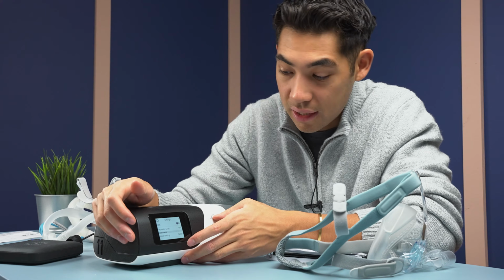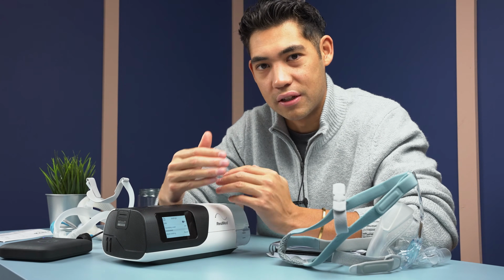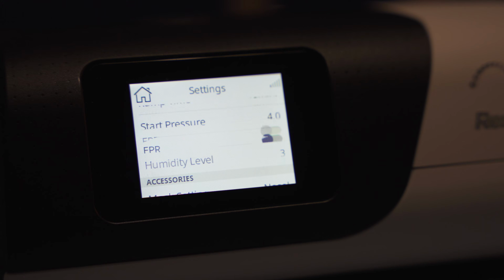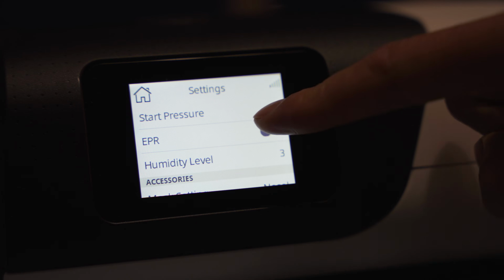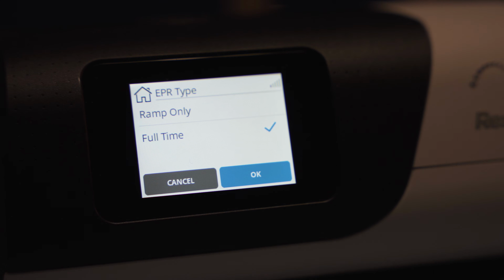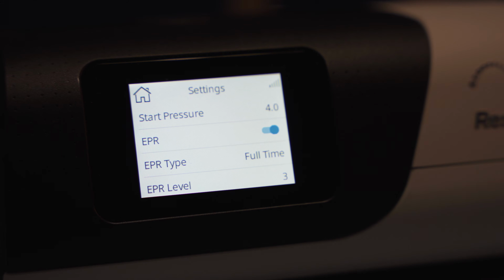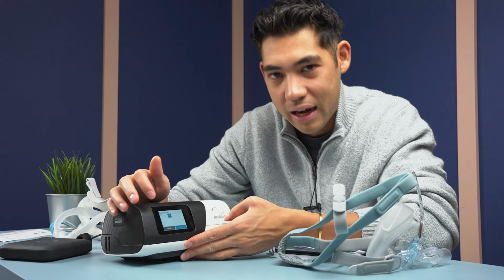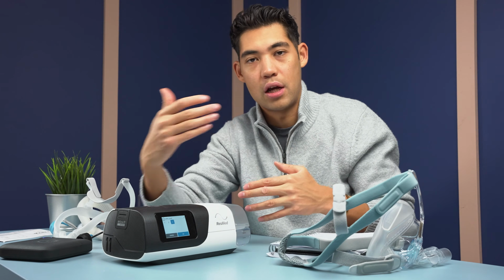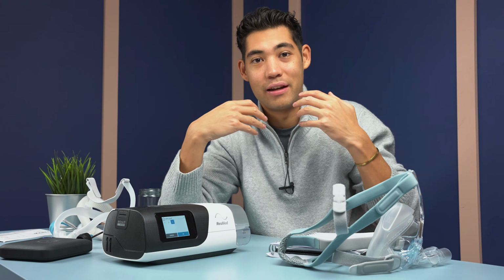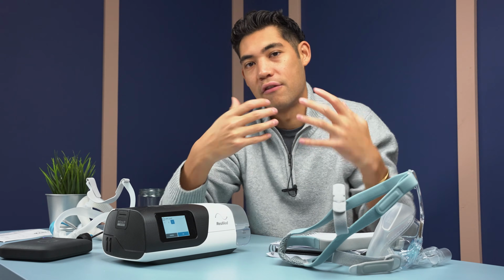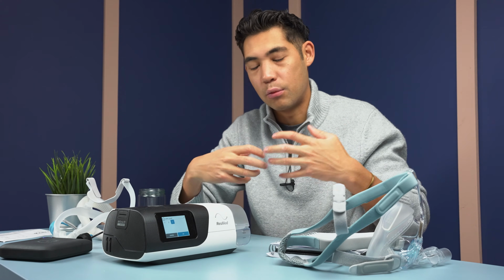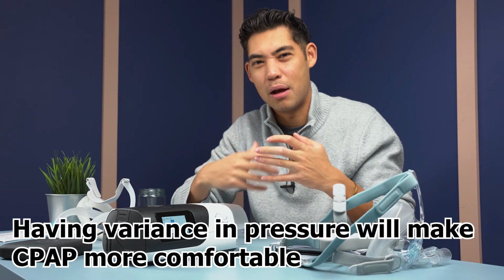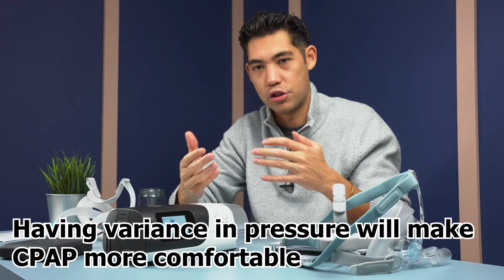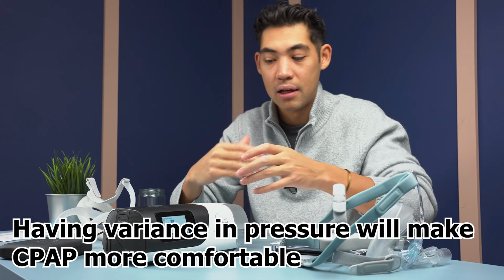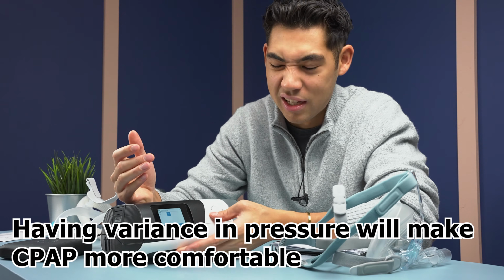So our pressure relief settings, or our EPR, is just how the machine is going to fluctuate when you exhale. So if we turn on the EPR here and we have EPR type ramp only, we can have it full time as well. And then we can adjust the level, so 1, 2, 3. And having the change in the pressure it's giving you as you inhale and exhale is gonna make you feel a lot more comfortable with the CPAP. You're gonna find that when you first start using CPAP and you exhale, it might be kind of hard to blow against the pressure that it's blowing back at you. So having your EPR, your pressure relief settings on, is really important.